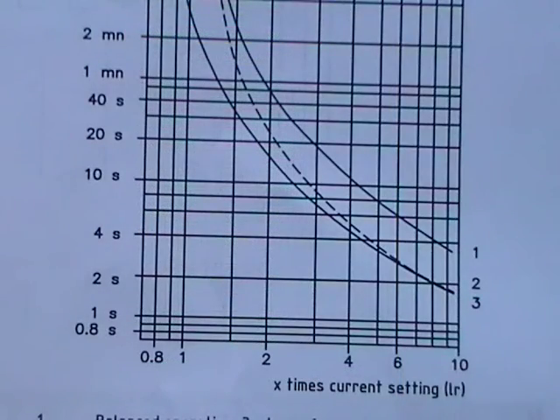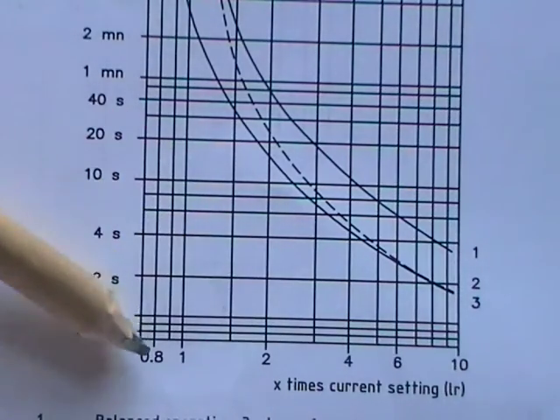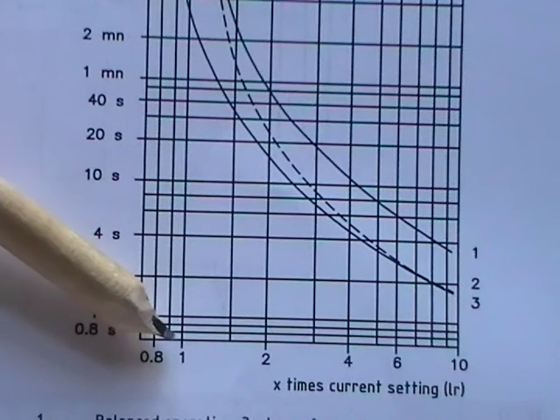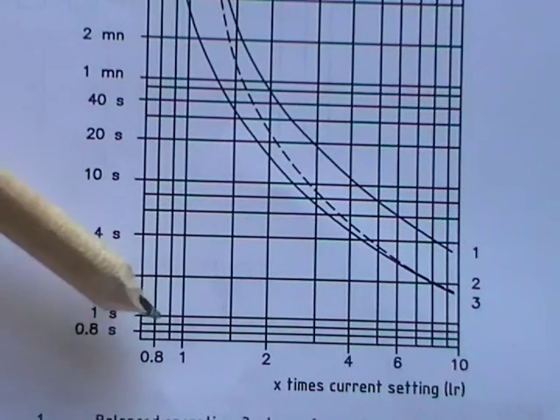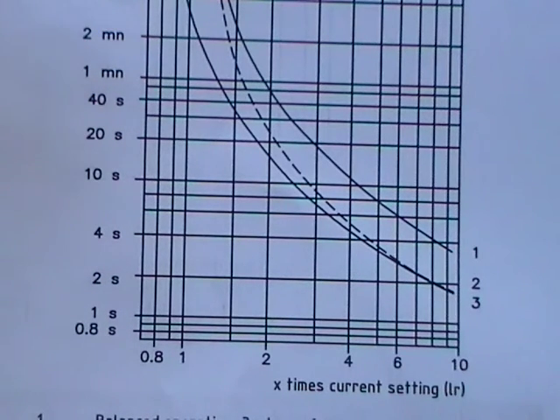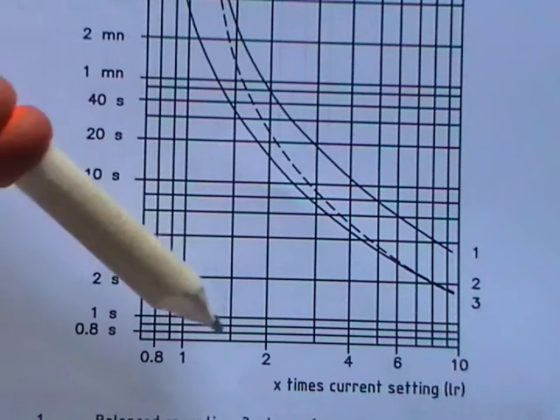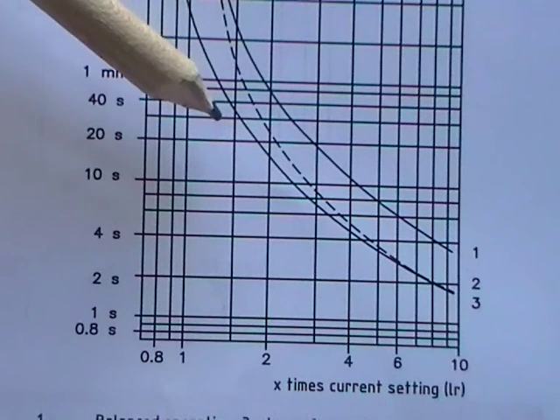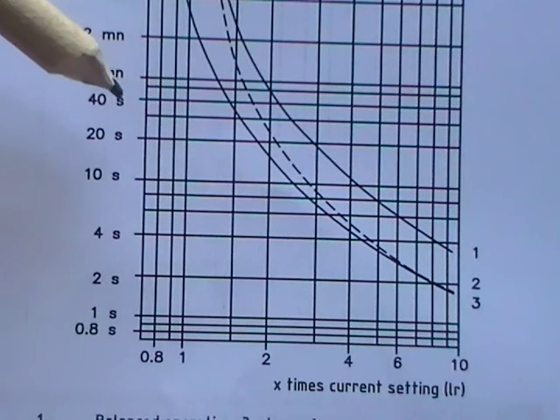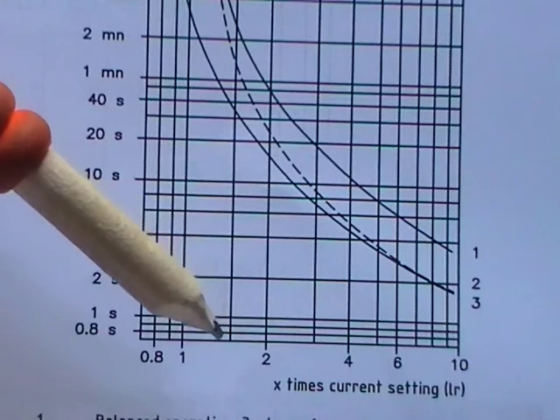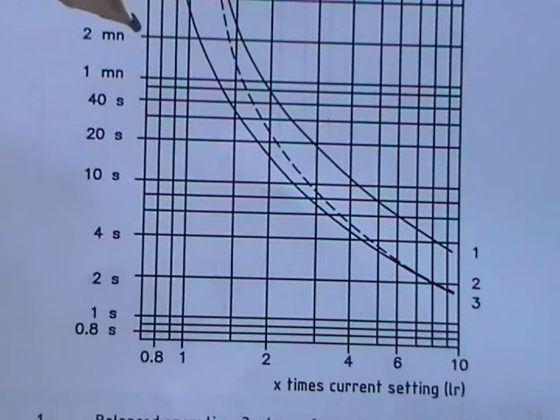Moving in a bit closer so you can actually read the numbers, we see just the same information. 1 being the current rating, or the setting on the trip. So as I say, if you set it for 10 amps, then at 10 amps it will run for a warm motor to just under 4 minutes. We on there? Yes? No? At 15 amps it would run for 30 seconds, coming across here on that line, 30 seconds. But also at 15 amps a cold motor would run for 2 minutes.